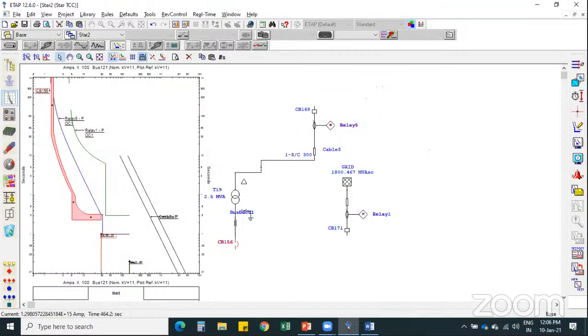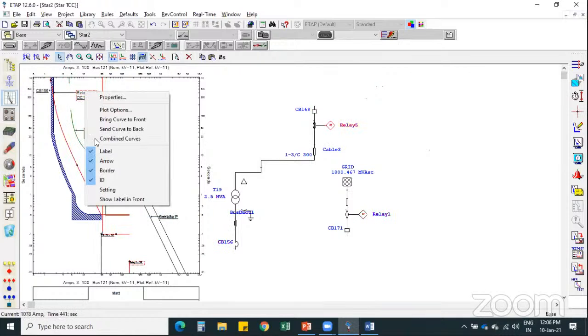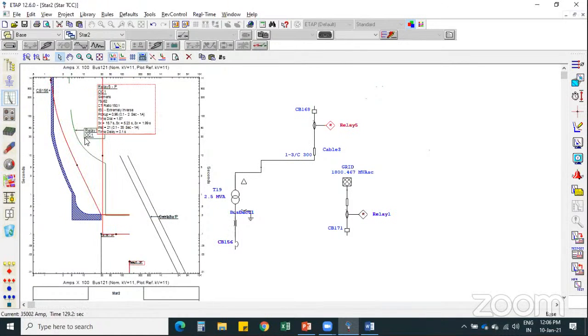And here we can see this current is displayed in terms of the 11 kV. So if we change the transformation ratio to 0.433, then we will get 3600 ampere over here. So this is how the relay coordination is done with the help of ETAP. With the help of ETAP, we can also have the setting parameters, that is, what settings we have adopted can also be cross-checked with this plot.